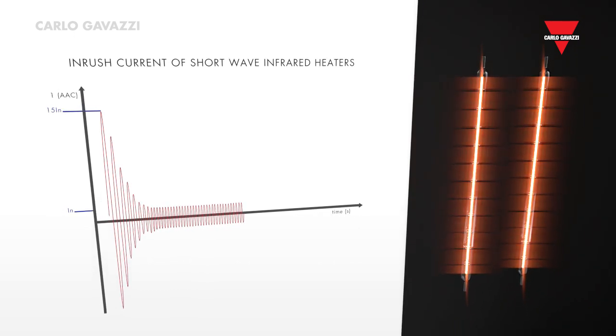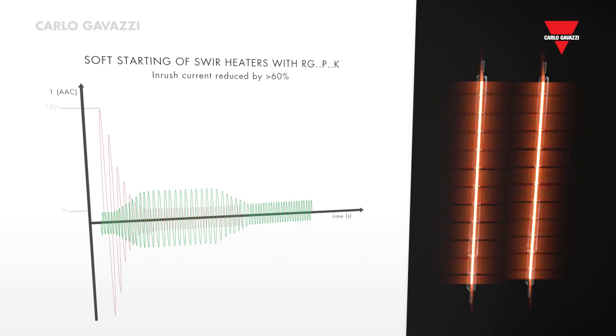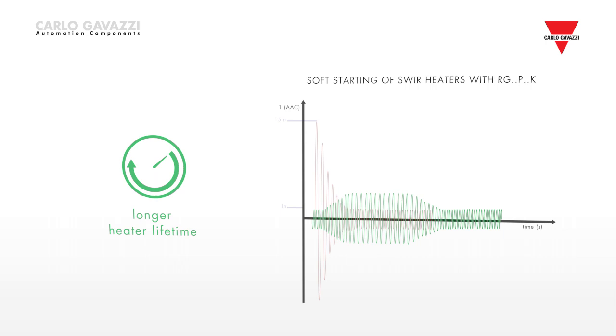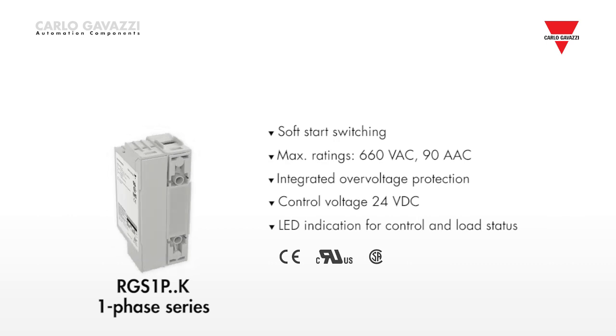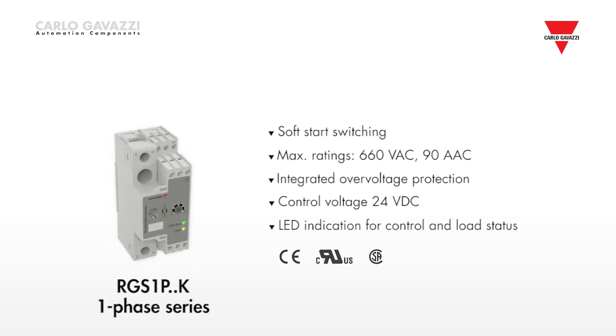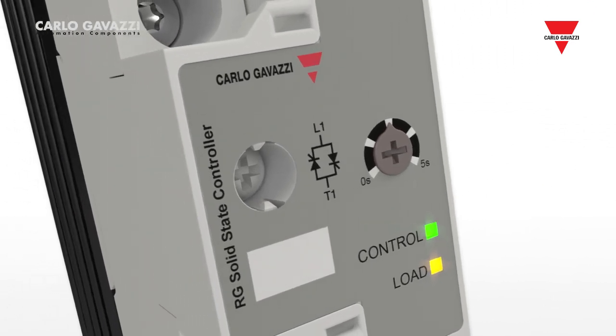The RGS1PK and RGC1PK single-phase soft-starting solutions eliminate this issue by smoothly regulating the voltage and the current. This switching method also results in an extended heater lifetime. The RGS1PK offers a maximum rating of 90 amps. Integrated protection prevents damage from overvoltage. LEDs are used to indicate both the control and the load status. The soft start timing is settable to a maximum of 5 seconds through a knob at the front.